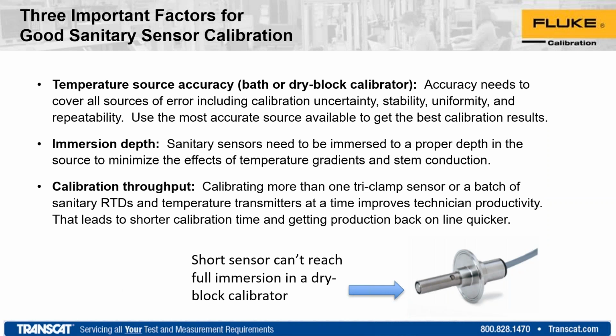All right. The things you want to consider with the temperature source are actually many things. There's uncertainty that can come from stability, uniformity, repeatability, immersion depth. Different things can cause or influence your overall uncertainty in the process. So in order to get the best calibration, you've got to consider what you would be testing in what particular product or heat source. And sometimes you give up some of the benefits of, say, a dry well, some of the speed and cleanliness of no fluids, because you can't accommodate a short sensor. You're just not going to be able to immerse it far enough, and you're probably not going to get the thermal conduction that you need to get a good reading.